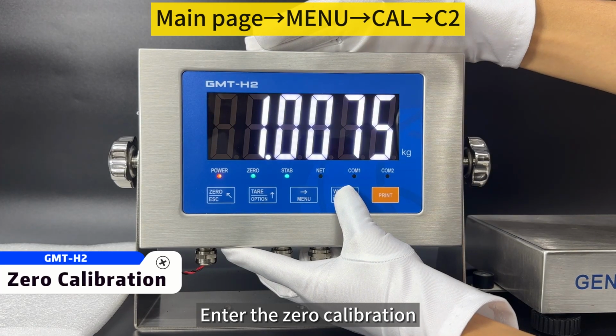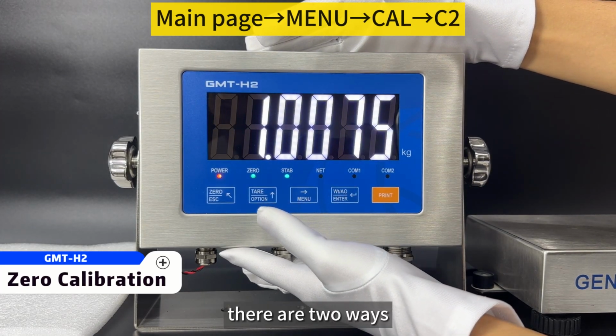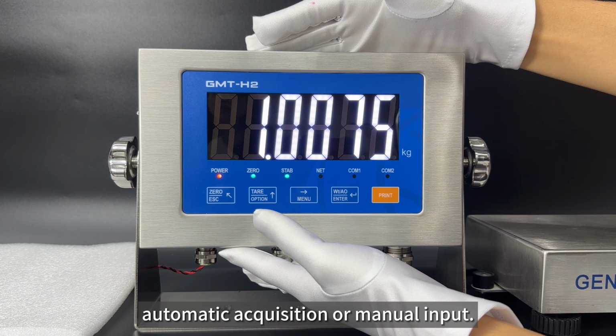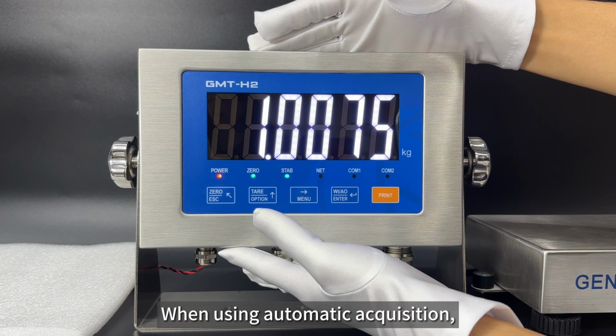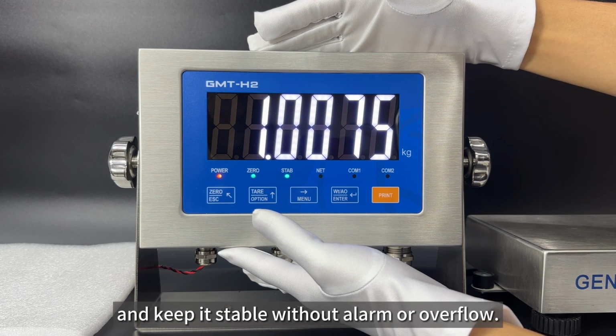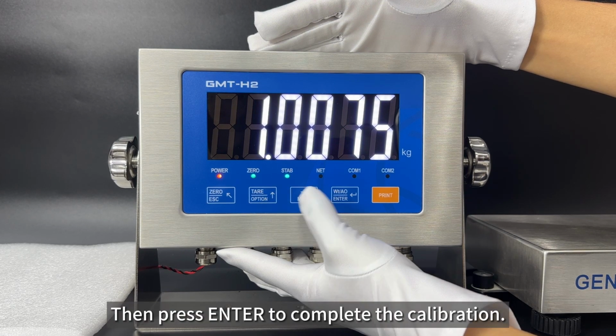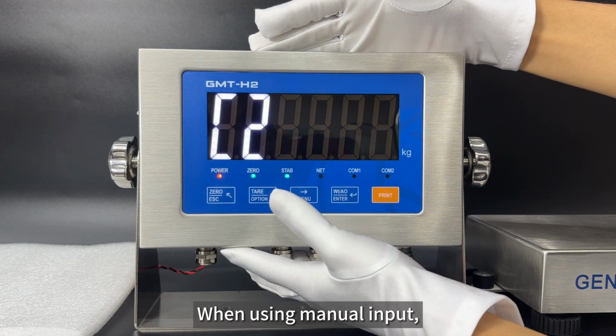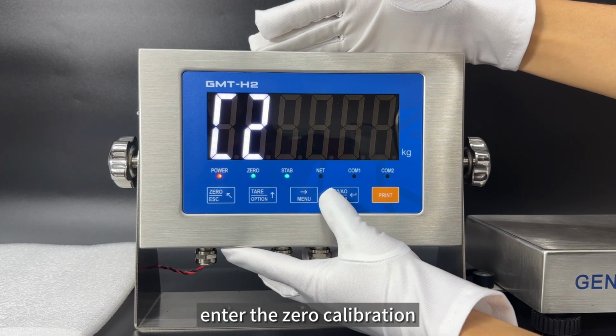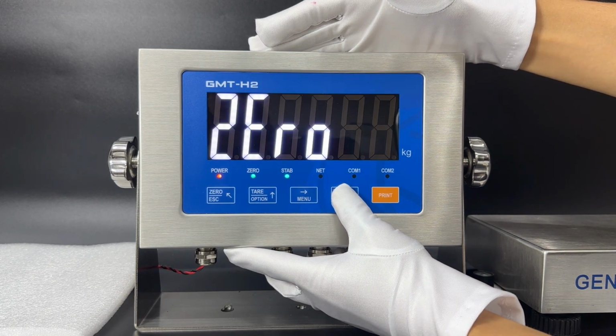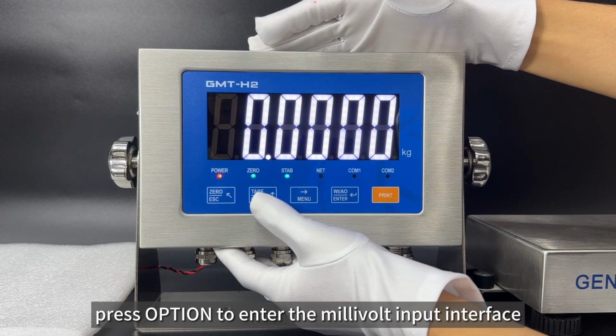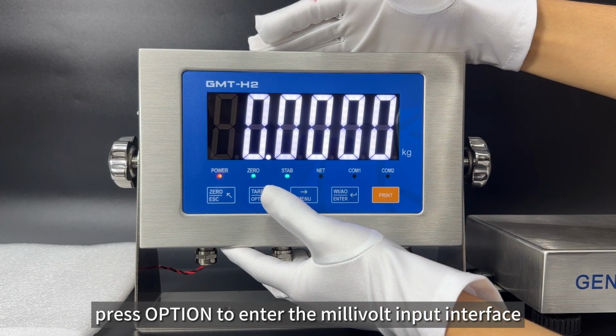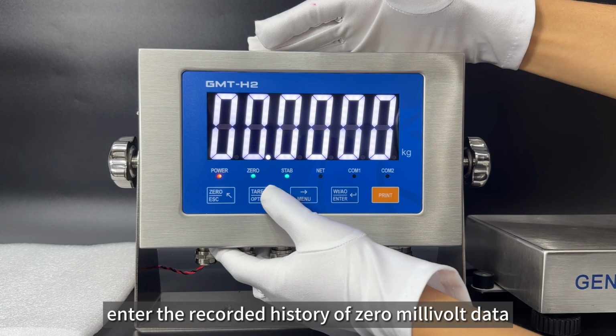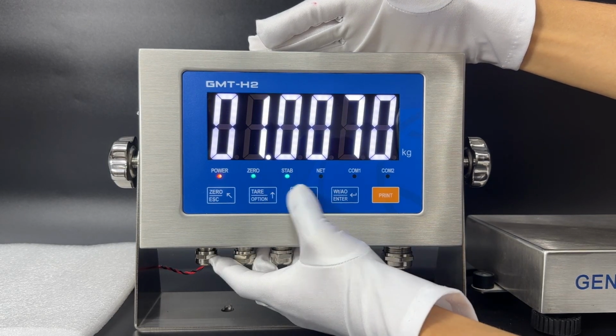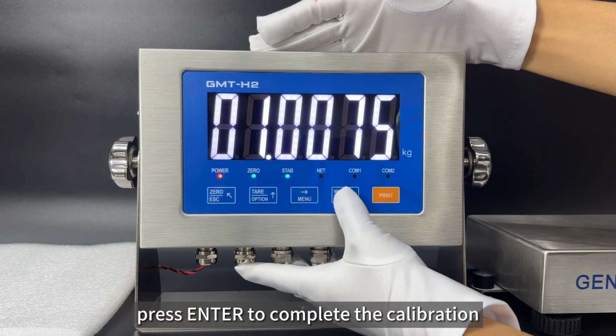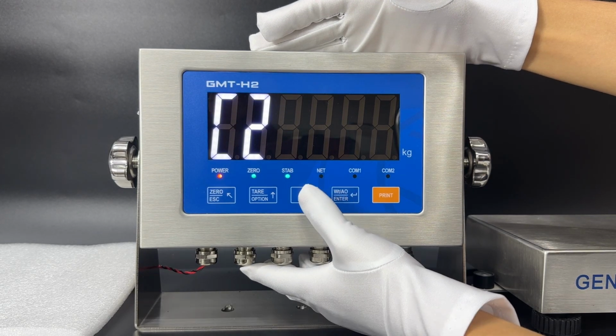Enter the zero calibration. There are two ways: automatic acquisition or manual input. When using automatic acquisition, clear the scale and keep it stable without alarm or overflow. Then press enter to complete the calibration. When using manual input, enter the zero calibration. Press option to enter the millivolt input interface. Enter the recorded history of 0 millivolt data. Press enter to complete the calibration.